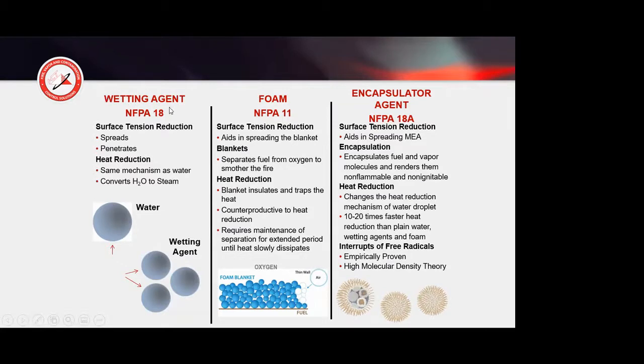There was an NFPA standard, still is, NFPA 18, that's wetting agents. And basically this is, hey, we're going to reduce the surface tension of the water. It's going to help it to spread and penetrate. But we'll note that the heat reduction is the same as water, because we're going to take the outer surface and we're going to convert it to steam. If we have a reduction in the surface tension, we're going to get slightly smaller droplets, which means we're going to get more steam conversion, which means we're going to get marginally better heat reduction.